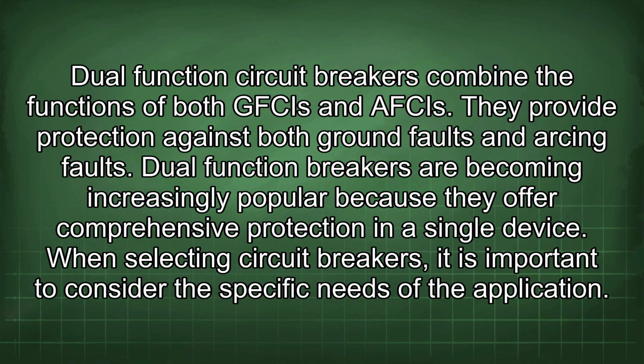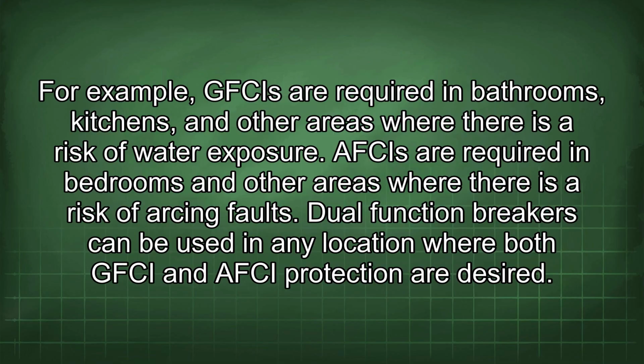Dual-function circuit breakers combine the functions of both GFCIs and AFCIs. They provide protection against both ground faults and arcing faults. Dual-function breakers are becoming increasingly popular because they offer comprehensive protection in a single device. When selecting circuit breakers, it is important to consider the specific needs of the application. For example, GFCIs are required in bathrooms, kitchens, and other areas where there is a risk of water exposure. AFCIs are required in bedrooms and other areas where there is a risk of arcing faults. Dual-function breakers can be used in any location where both GFCI and AFCI protection are desired.